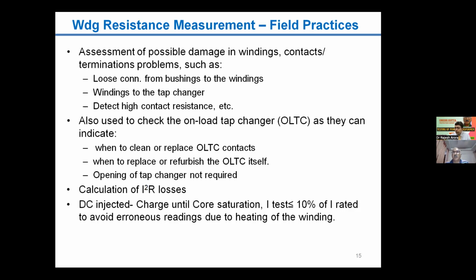This is a very important test which gives insight not only about the health of the winding of the transformer, but also about loose connections, terminations, bushing to winding, issues in the tap changer, and high resistance that has developed between different terminations and connections. These kinds of issues may also be checked through winding resistance measurement. Also, you can check the on-load tap changer, as I mentioned earlier. Then this test is also done to calculate I squared R losses.